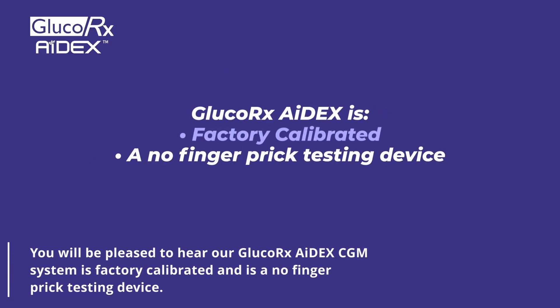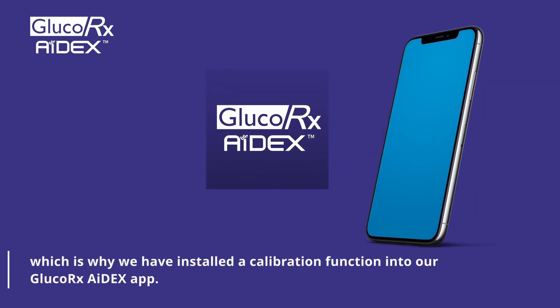You will be pleased to hear our GlucoRx AiDEX CGM system is factory calibrated and is a no finger prick testing device. However, GlucoRx understands having the option to calibrate for peace of mind is a desirable feature in a CGM, which is why we have installed a calibration function into our GlucoRx AiDEX app.